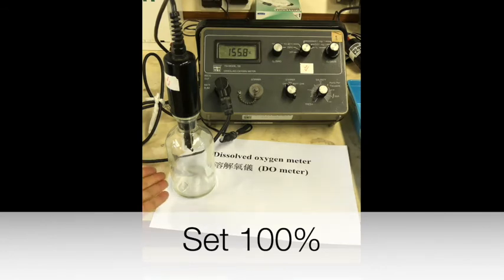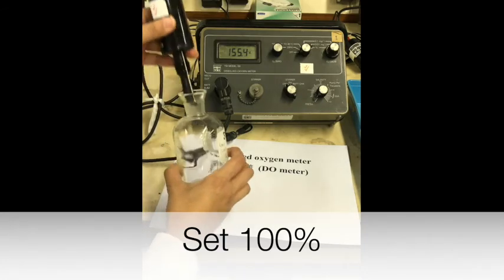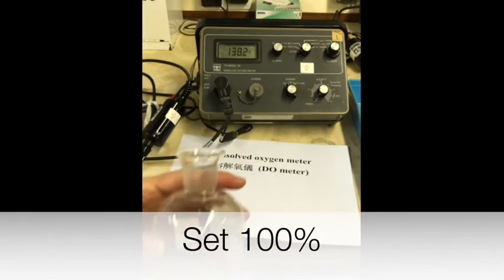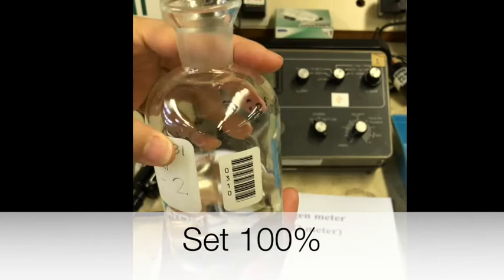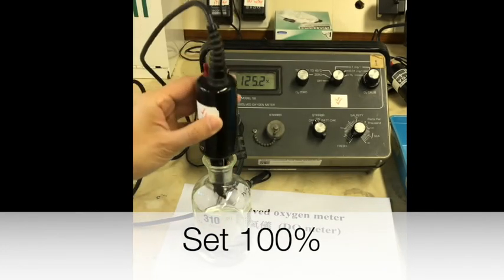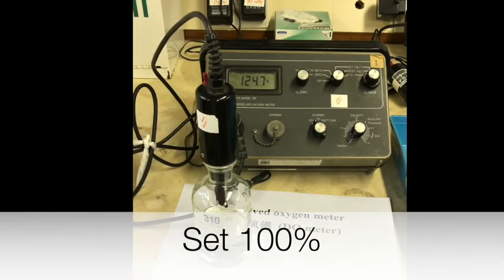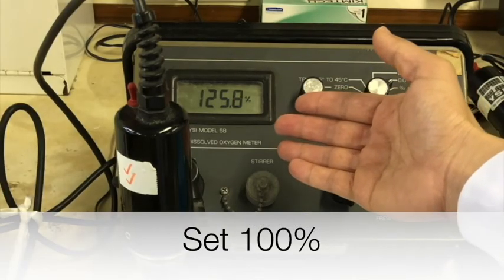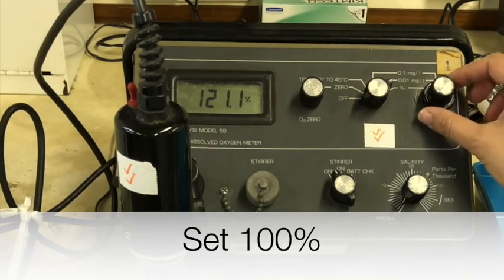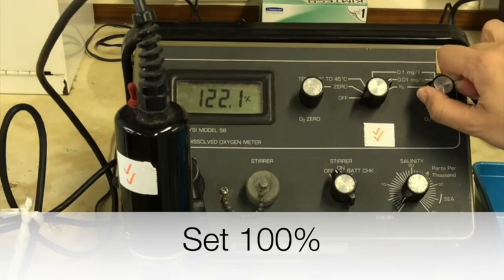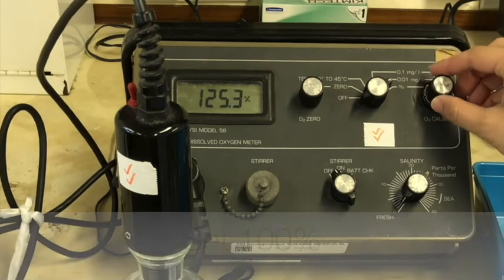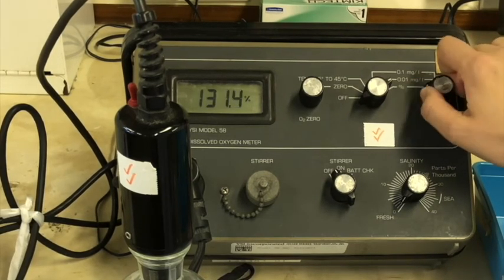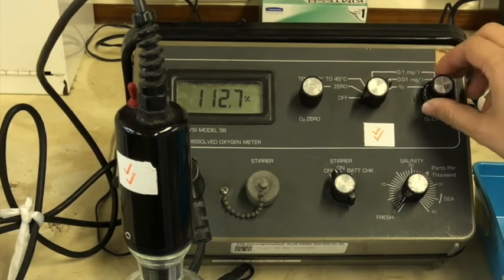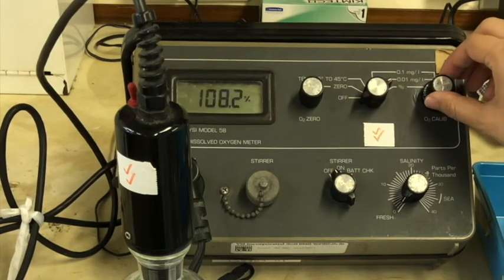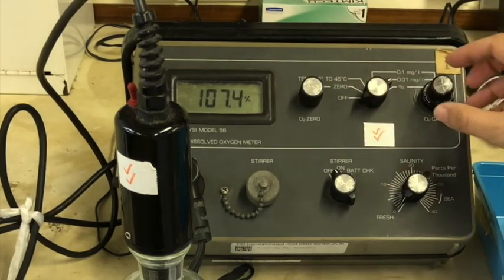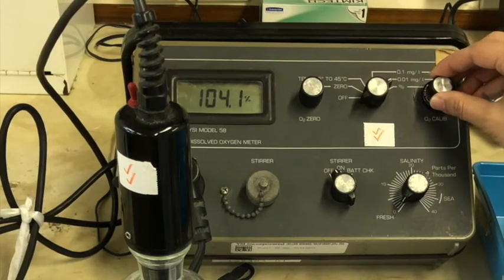Place the electrode in a BOD bottle containing about 1 inch of water to provide a 100% relative humidity calibration environment. Fill the BOD bottle with deionized water and place the electrode back into the BOD bottle. And adjust the display to 100%. And adjust the reading. Adjust the display to 100%. As you can see, the reading is dropping. Adjust the knob slowly until it reaches 100%.